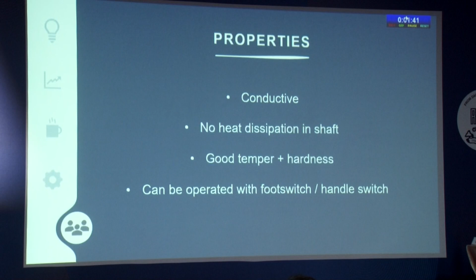So with that idea in mind, Chennai Surgicals helped me develop the first prototype, which we developed in 20 gauge. As you can see here, it comes with a 2-cylinder system, an outer cylinder and an inner cylinder. The inner cylinder is connected to one pole of the diathermy, the other to the other pole. The inside cylinder connects to one prong and the outside cylinder to the other prong. So only when the prongs come in contact, the circuit is completed and electricity passes through, and whatever tissue is in between will get cauterized. So this is the principle.